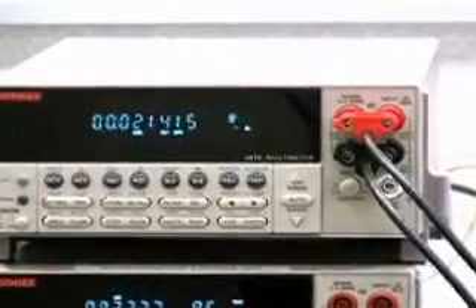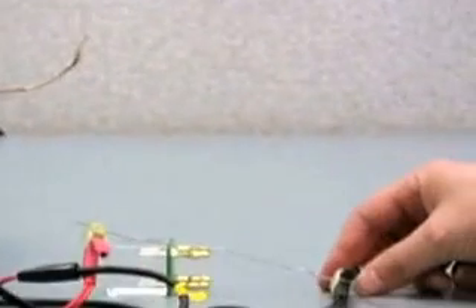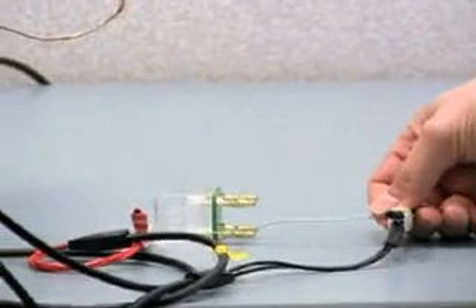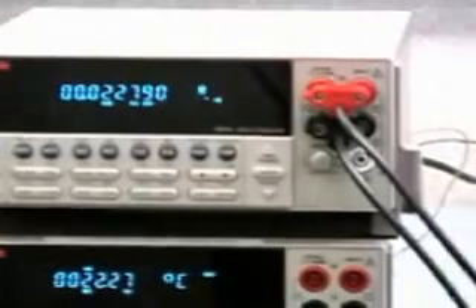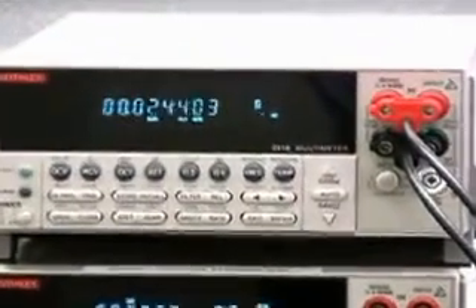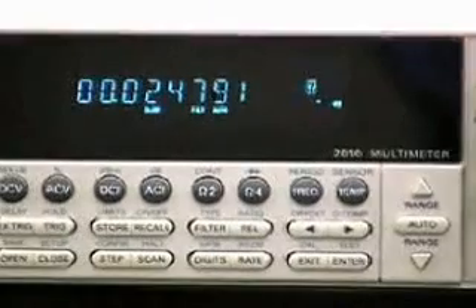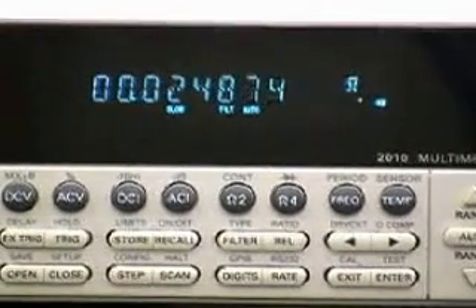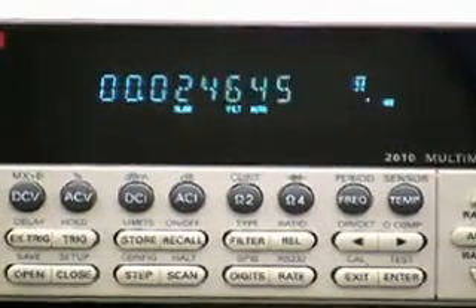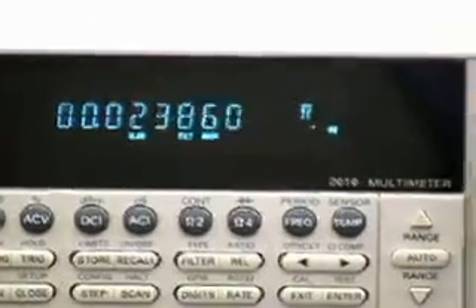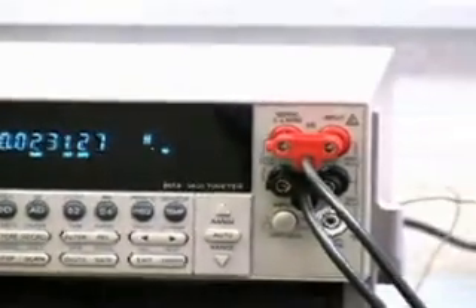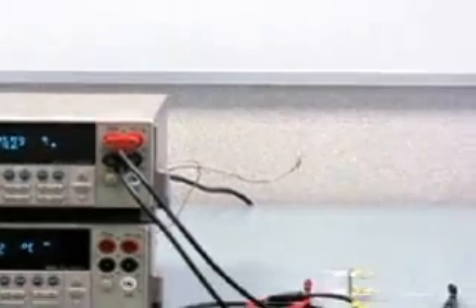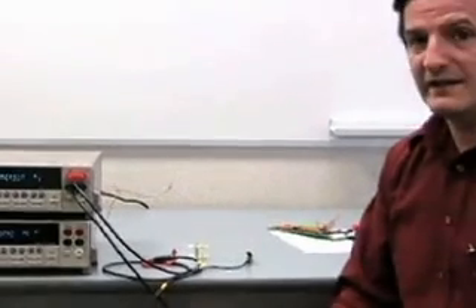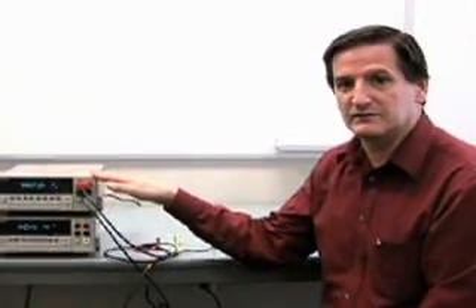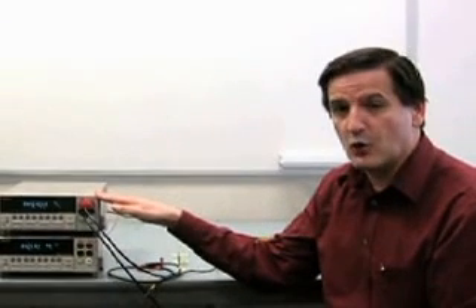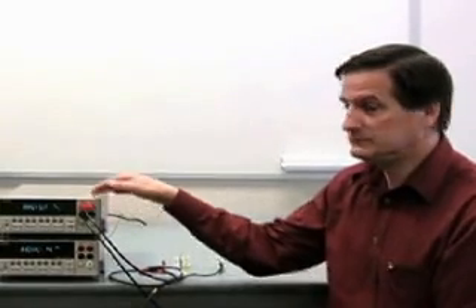I'm going to hold on to the lead again. Now watch the display. I'm heating up the lead. Whoa, it's going up higher and higher and higher. That's the thermal effects when measuring low resistance. Thermal effects are thermal EMFs. That's the biggest source of error when measuring low voltage. When you're measuring low resistance, it's really measuring low voltage. So the model 2010 has this offset compensation feature that is very good for low resistance measurements.